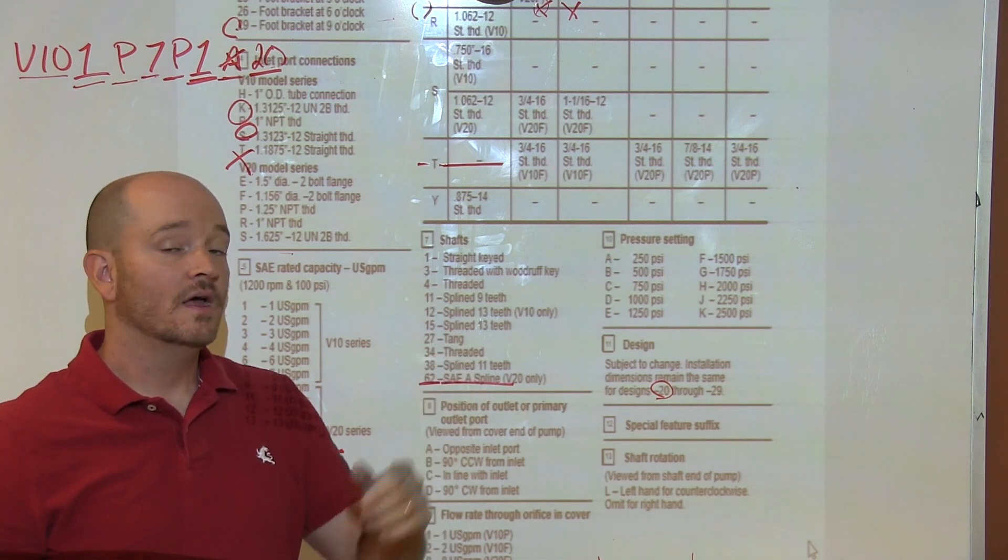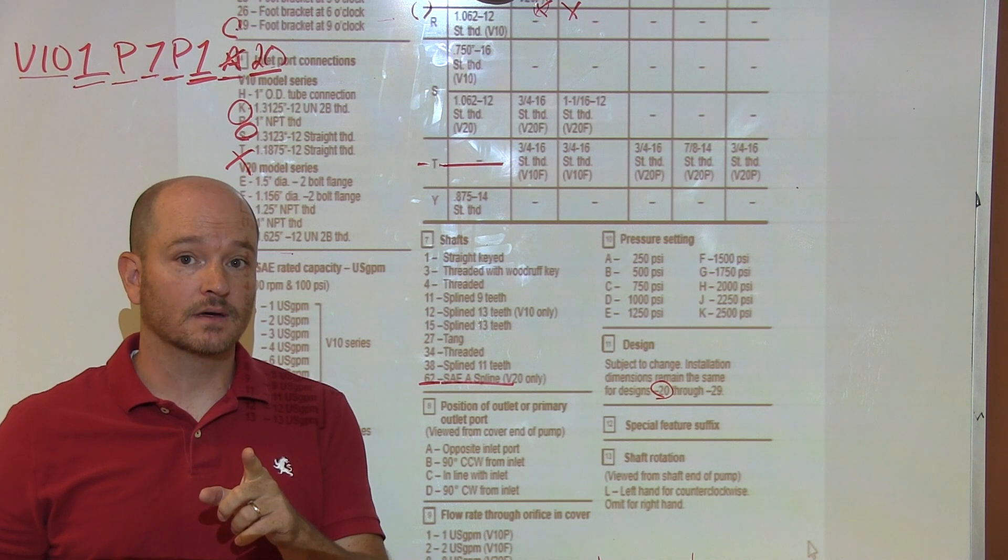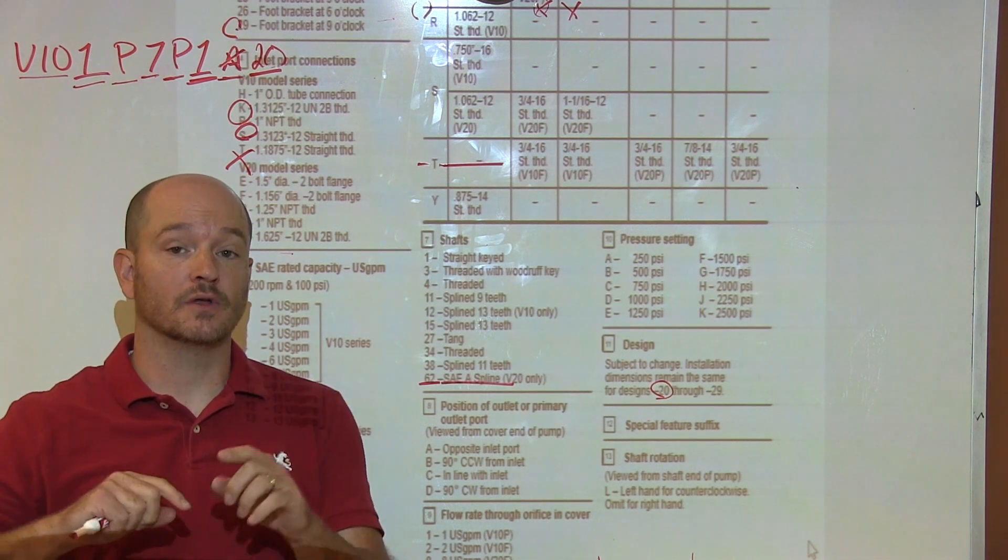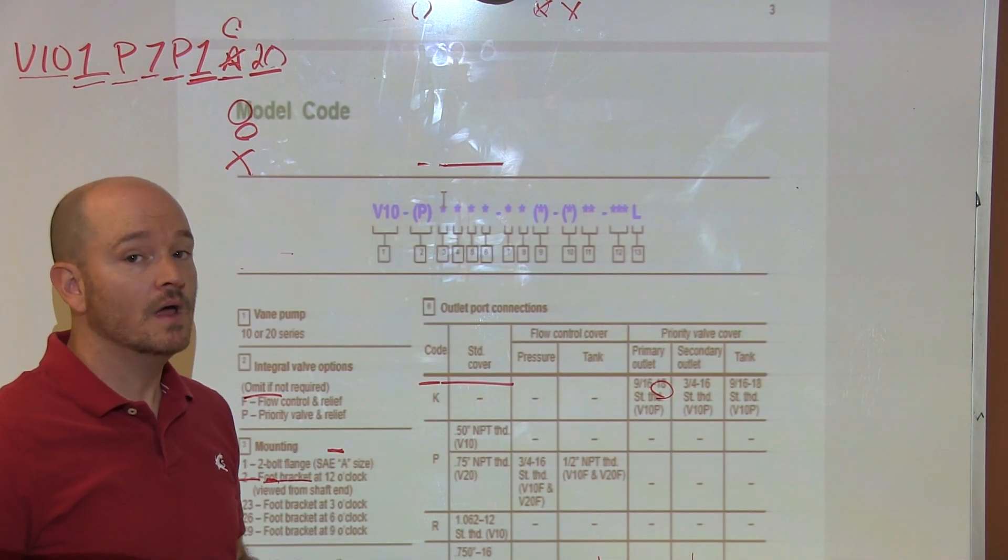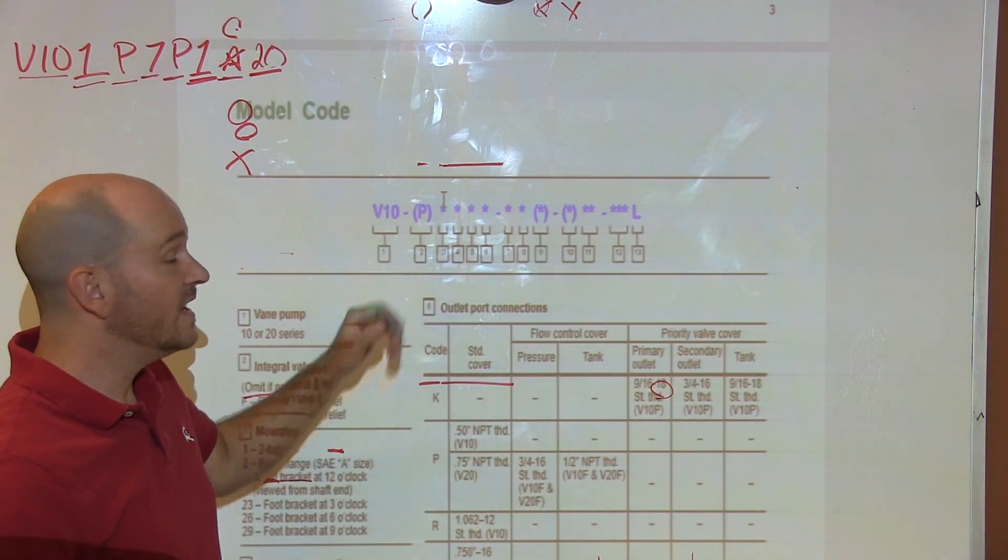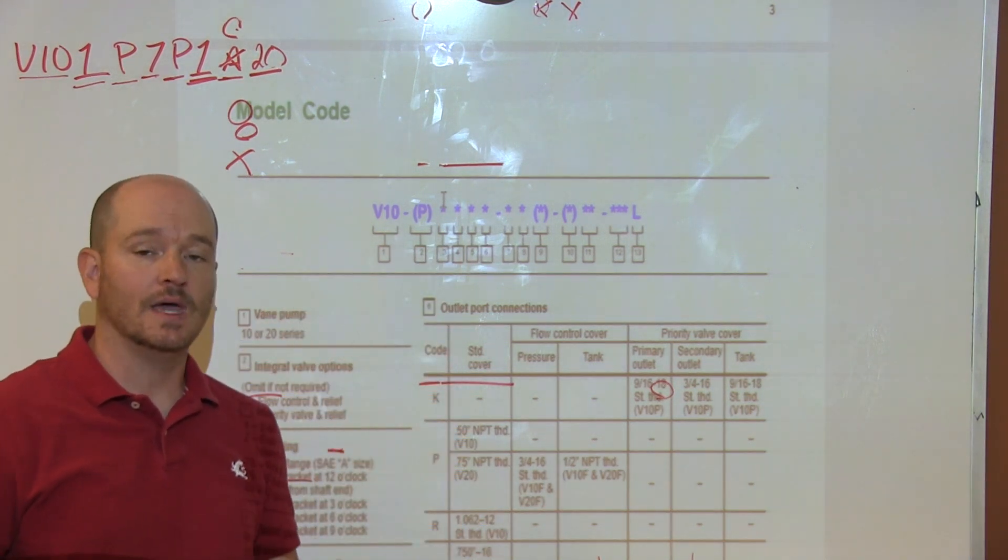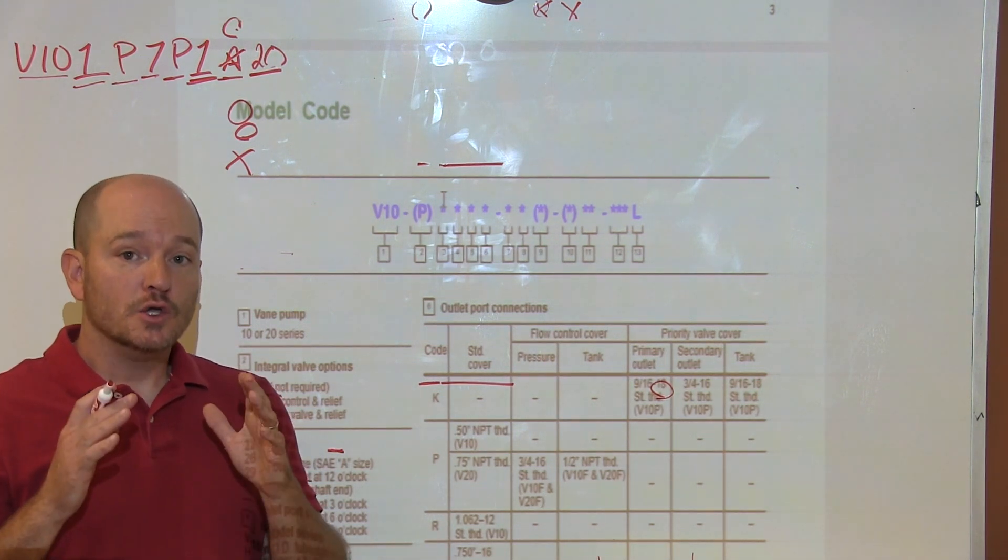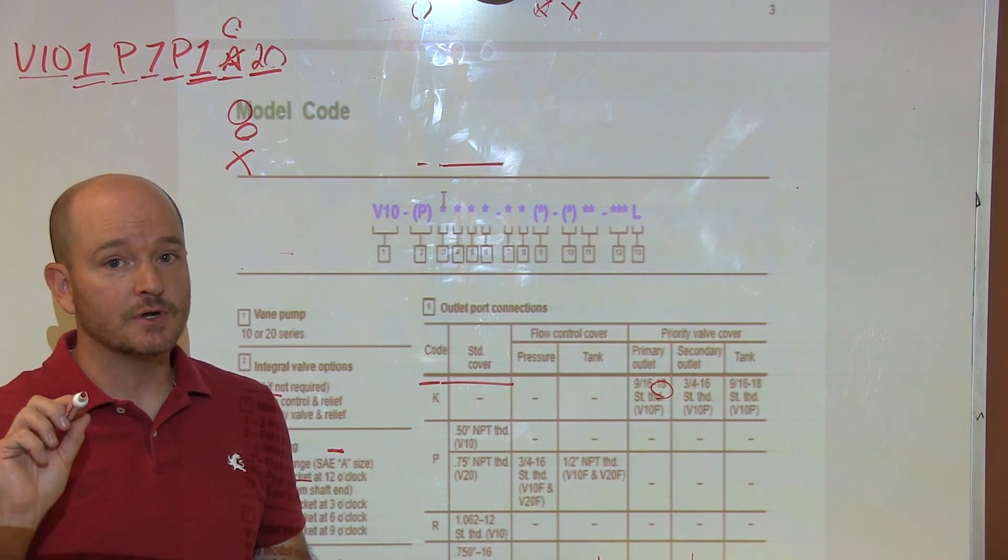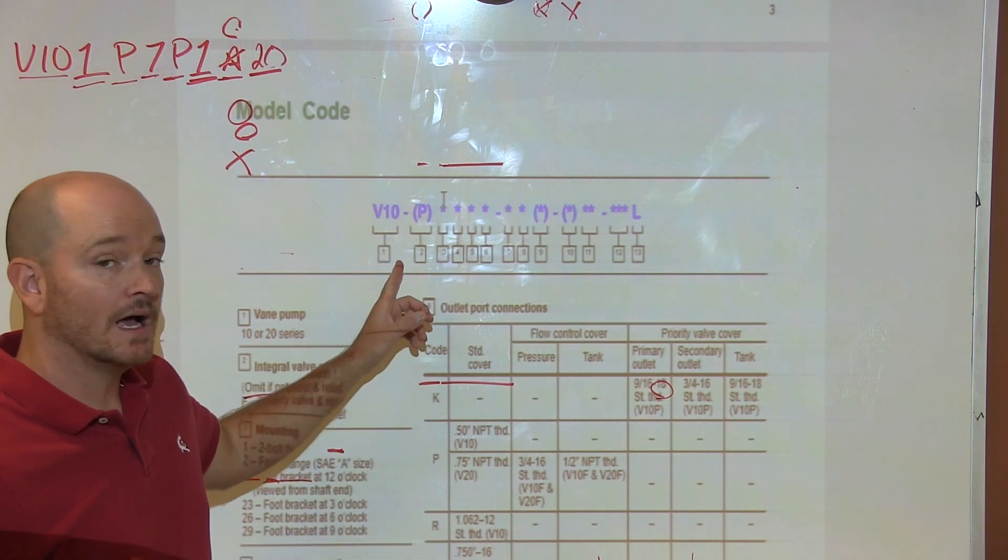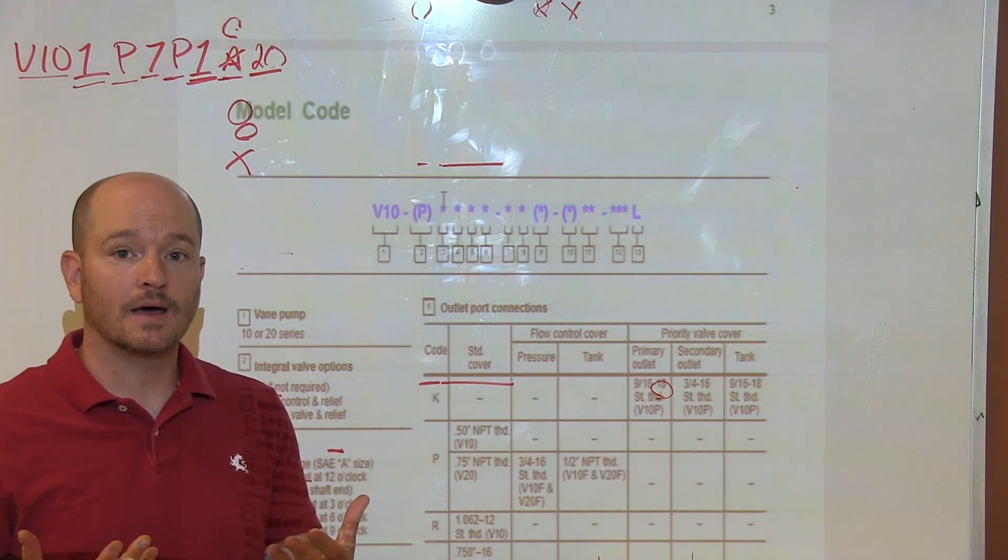It's manufacturer specific. There's no standard for model numbers, although they all tend to use this type of code here to break these down. By no means does the V always mean vane, and things like that. What does the 10 stand for? They're not always going to give you gallons per minute, they're not always going to give you displacement. Experience and a basic understanding of hydraulic pumps is absolutely required to break down the characteristics of a pump when you decode a model number using its manual.